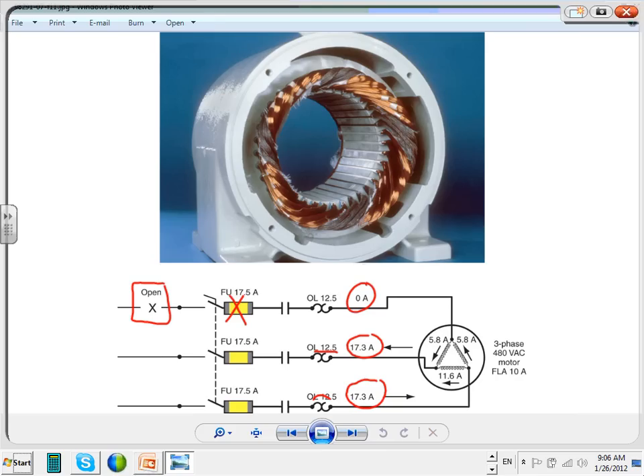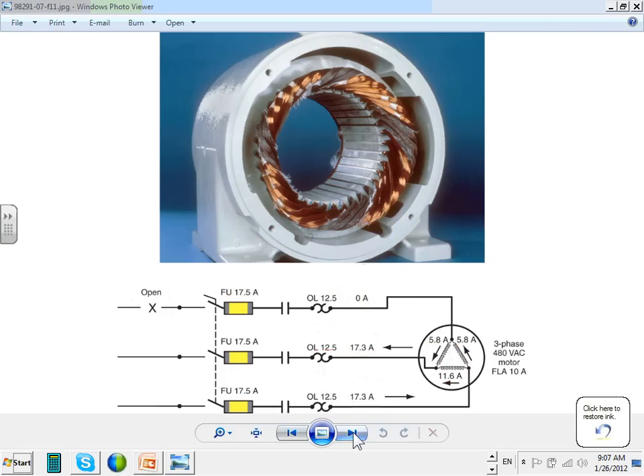But if we send Oladipo, big-headed Oladipo, he decided to put, I'm going to say just 19 here, 19 here, and 19 here, each one of them, oversize them. This will burn, and you're going to see the situation that you're looking at. So look at that, this coil, because in a delta, look how they spread, guys. In a delta, one coil is going to be burning, because each one of these is rated for 5.5. One coil is going to be burned. But who cares? You burn your motor. So this is an example of single phasing a delta motor. Not commonly used. A lot of places, guys, we use Y motors. But if you have a delta motor, also you're doomed if you single phase and you don't size the overload properly.